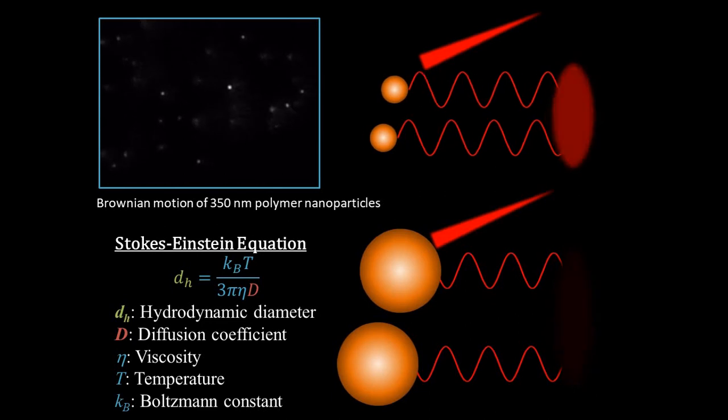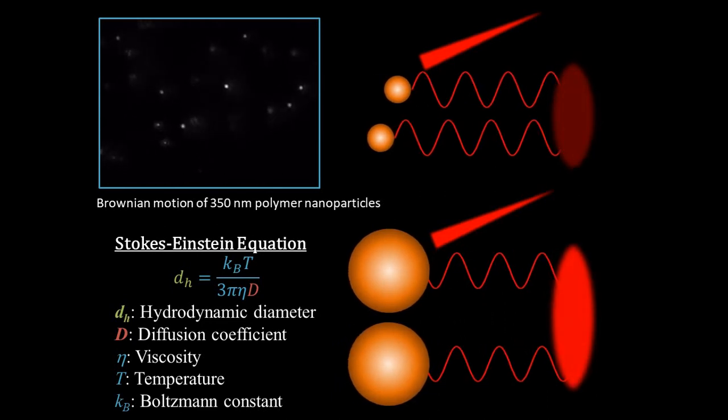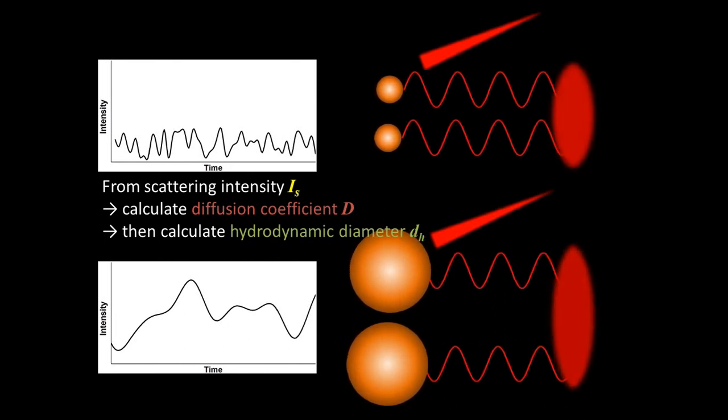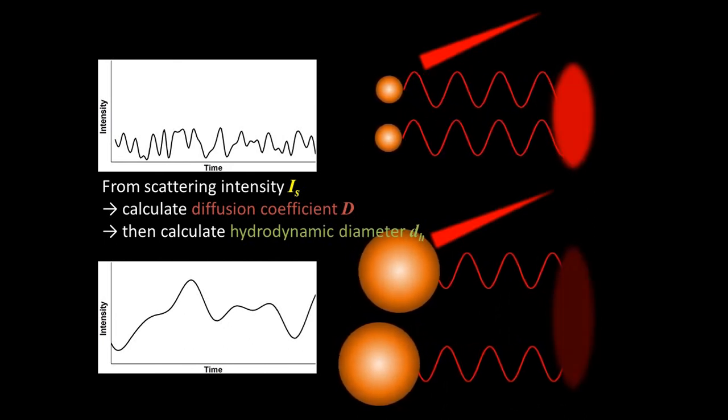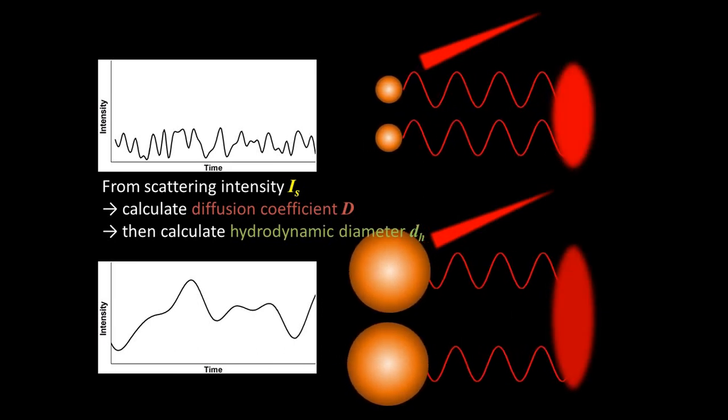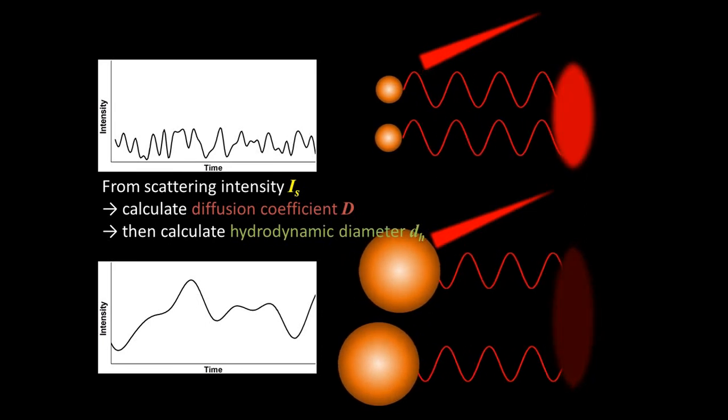Due to hydrodynamic drag, large particles move slower than small ones as modeled by the Stokes-Einstein equation. So small particles show a low intensity of scattered light with a high frequency of flickering, while large particles show a low frequency of flickering but scatter more light per particle. This flickering is related to the diffusion coefficient of the particle, and this diffusion coefficient is then used to calculate an average diameter.